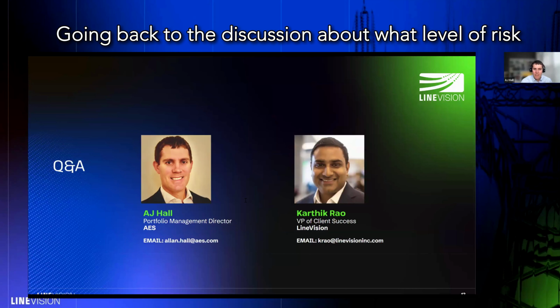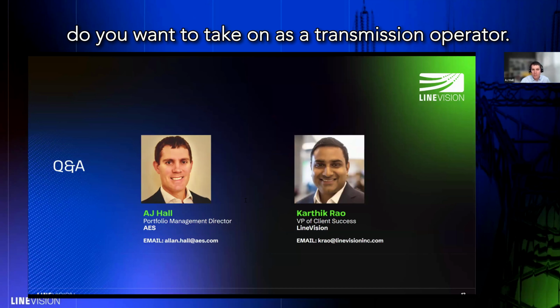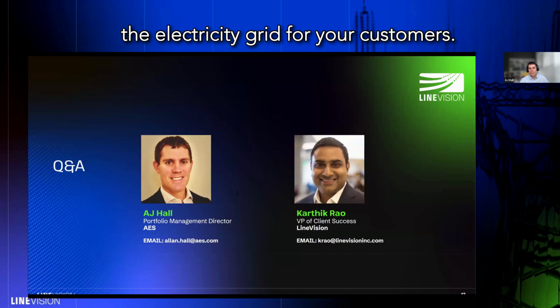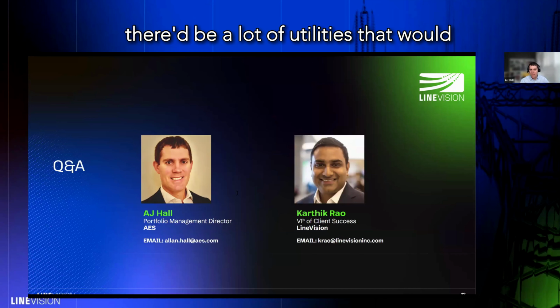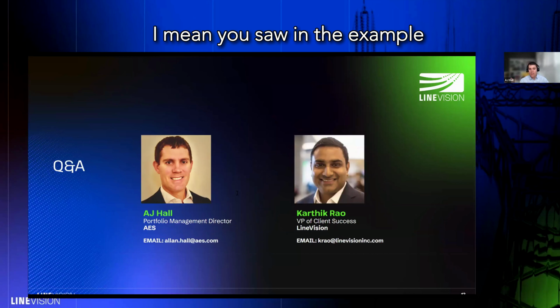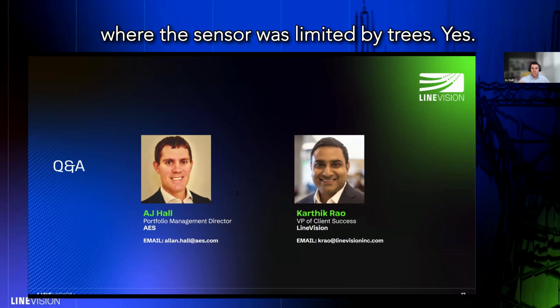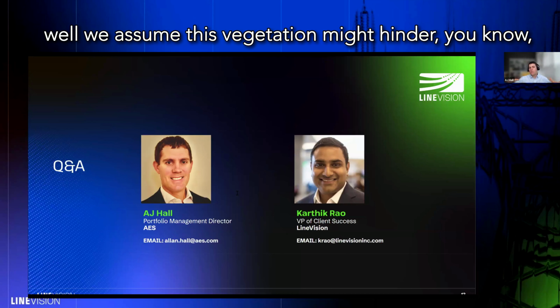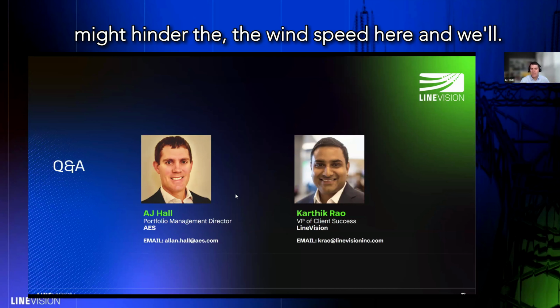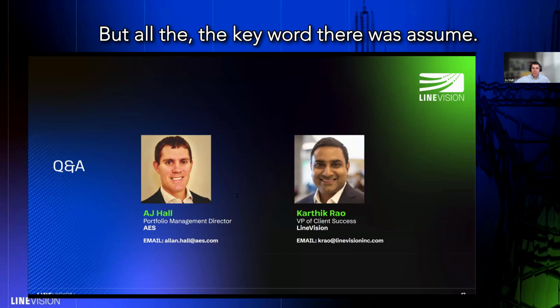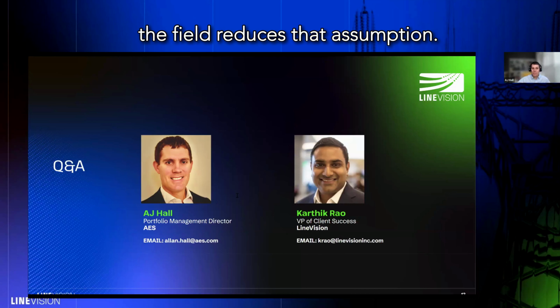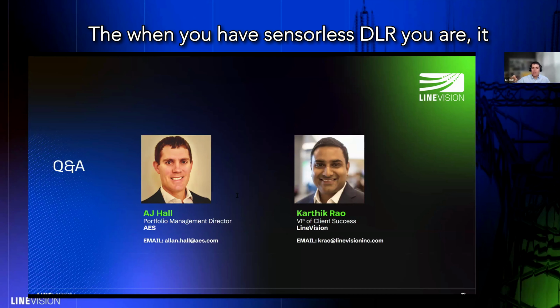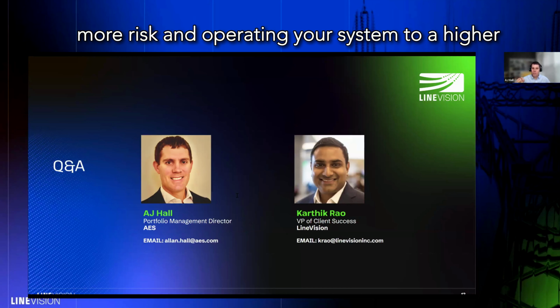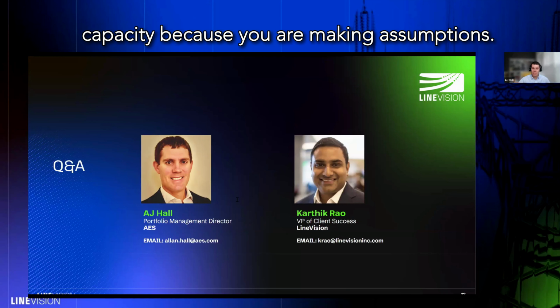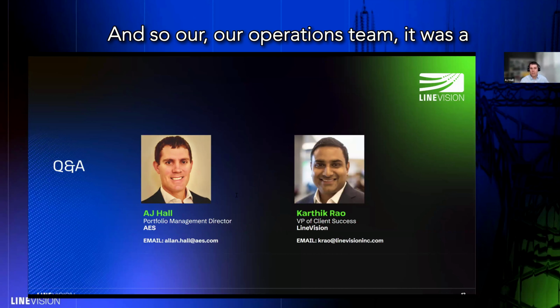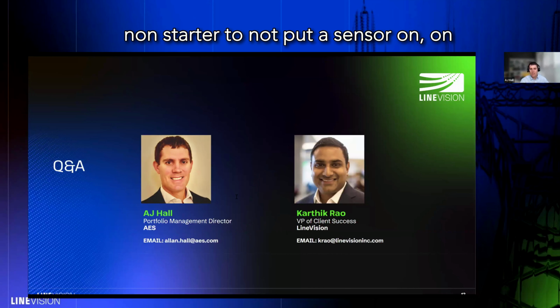Going back to the discussion about what level of risk you want to take on as a transmission operator, you're responsible for operating the backbone of the electricity grid for your customers. We did not feel comfortable using sensorless DLR, and I think a lot of utilities would echo this. You saw in the example where the sensor was limited by trees. There are technologies that assume vegetation might hinder wind speed, but the key word is assume, and having a sensor in the field reduces that assumption. With sensorless DLR it's hard to say you're not taking on more risk operating your system to higher capacity because you're making assumptions. For our operations team, it was a non-starter not to put a sensor on the system we could rely upon.